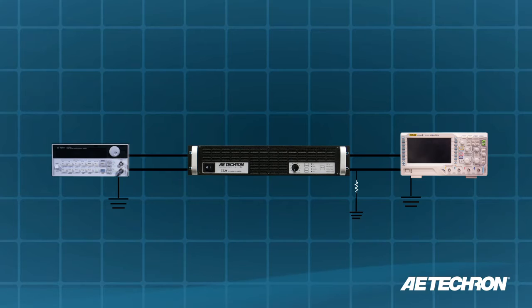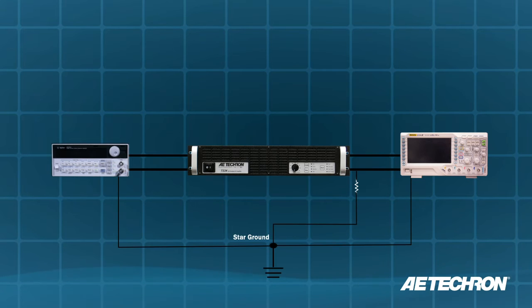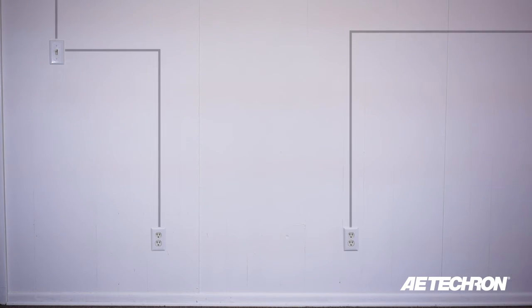To avoid this, it is recommended that a local master ground bus, also known as a star ground, be used in systems to limit differences in ground points. Outlets that are physically close together do not necessarily have equal grounds, as they may be on different circuits.